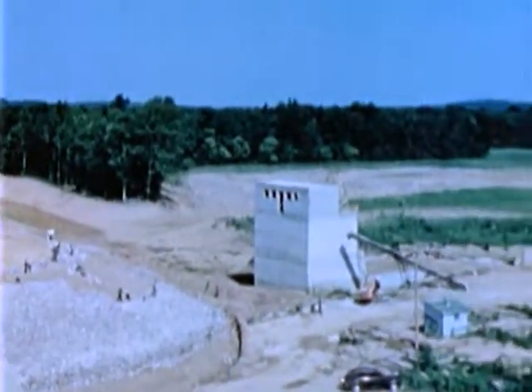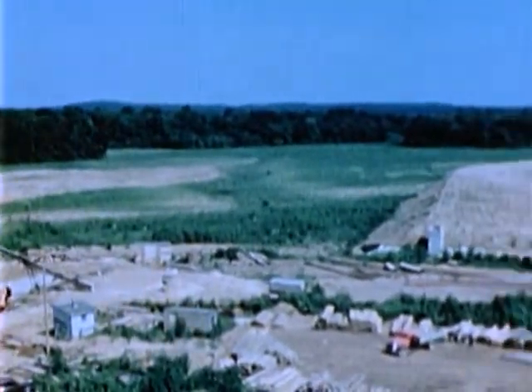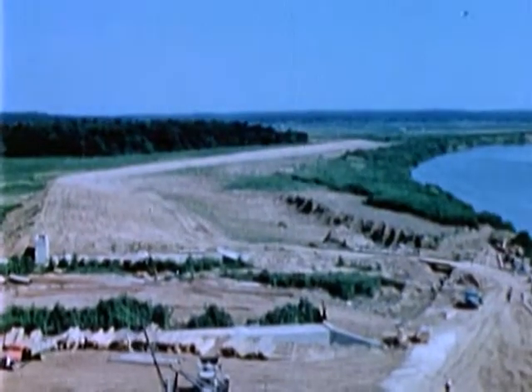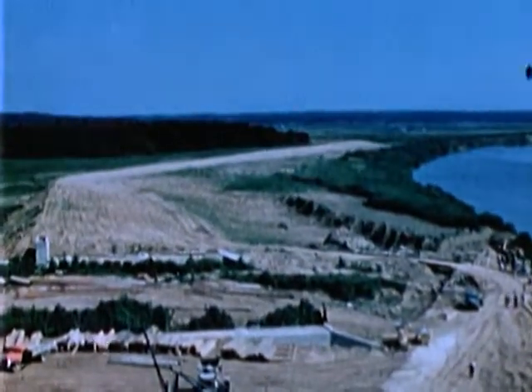Depending upon the size of the drainage area behind each dike, the capacity of the pumps installed at the 8 projects ranges from 16,000 to 250,000 gallons per minute. In the largest plant, where pumping is expected to be almost continuous during the mosquito breeding season, 6 electrically powered pumps were set in place. In more remotely located plants, where intermittent pumping is anticipated during the summer, automatic gasoline-powered pumps are used. The dewatering of the areas at the beginning of the mosquito breeding season is expected to require from 12 to 24 days each spring, depending on the size of the project.